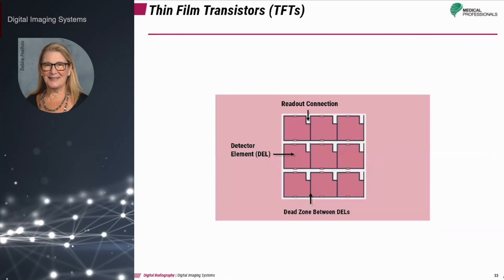The size of the detector elements determines the spatial resolution of a flat panel detector. As the size of the DEL increases, the spatial resolution decreases. This is very similar to when we talk about pixels in a matrix — the smaller the pixel size, the greater the resolution; the larger the pixel size, the less the resolution.